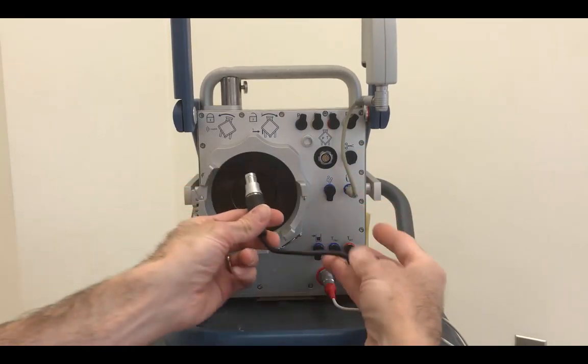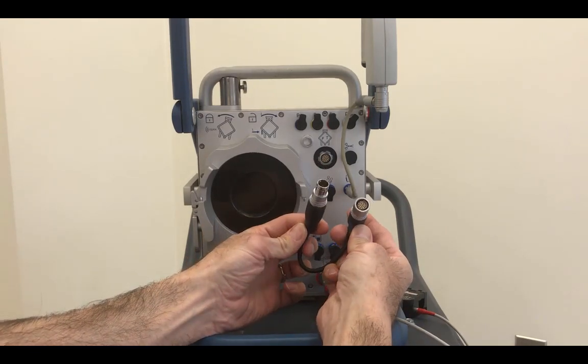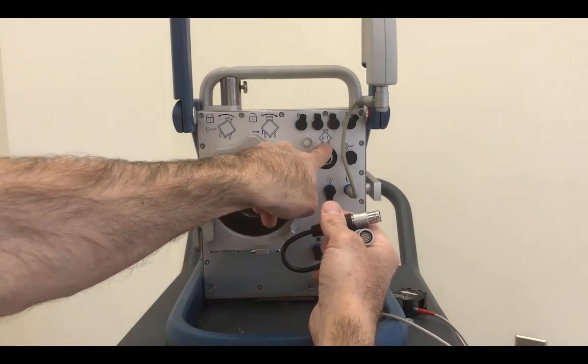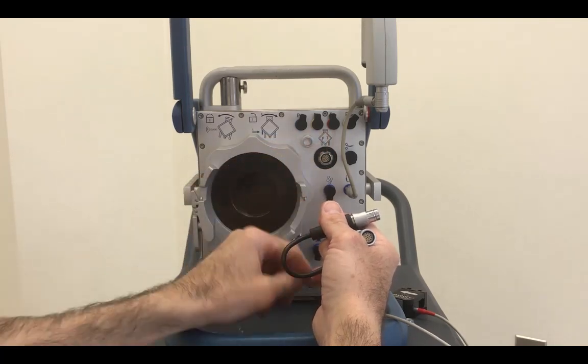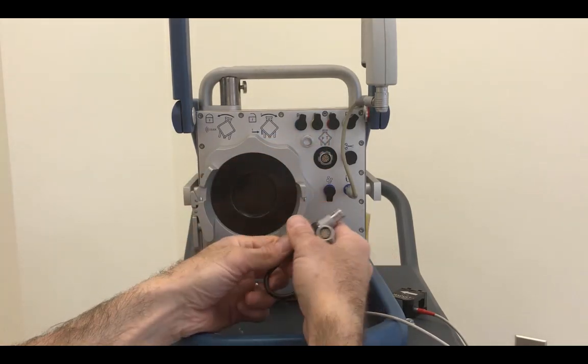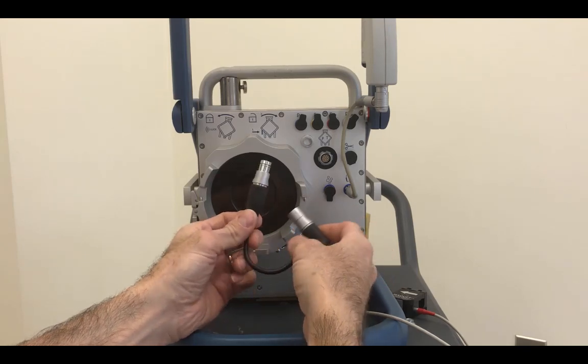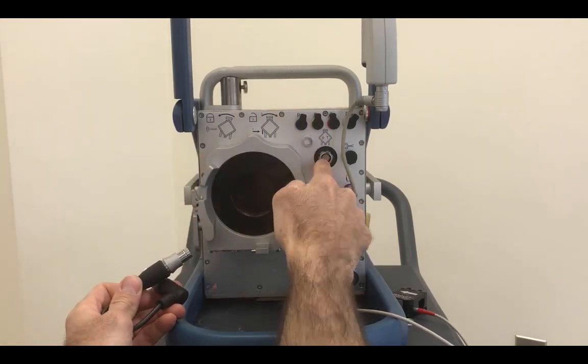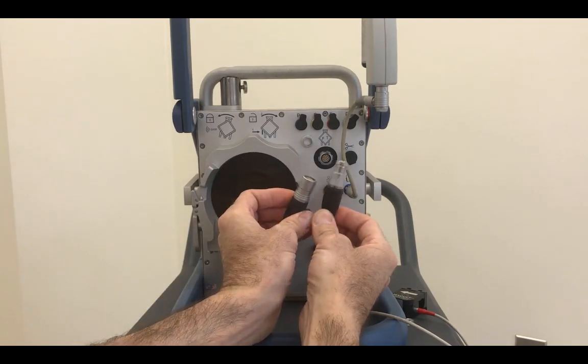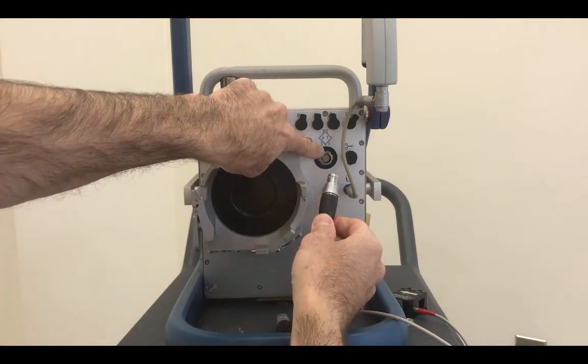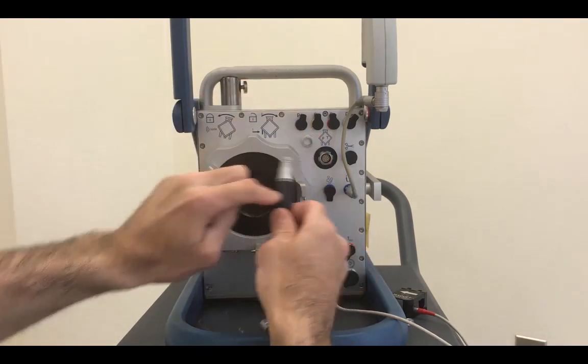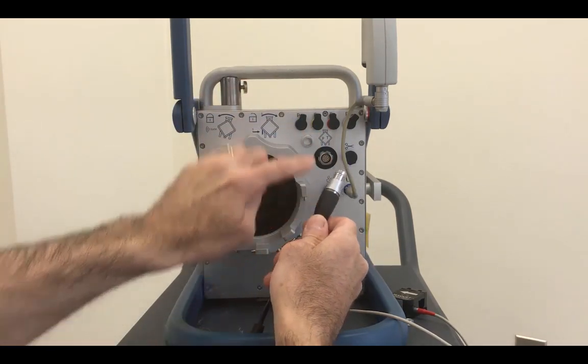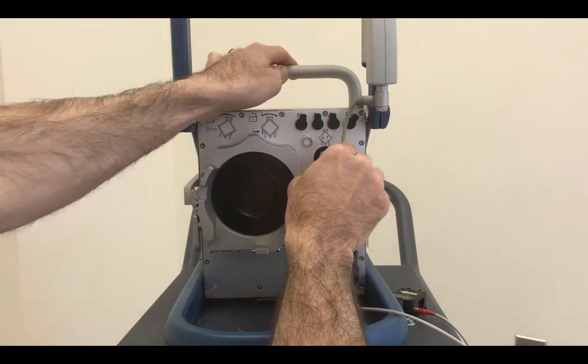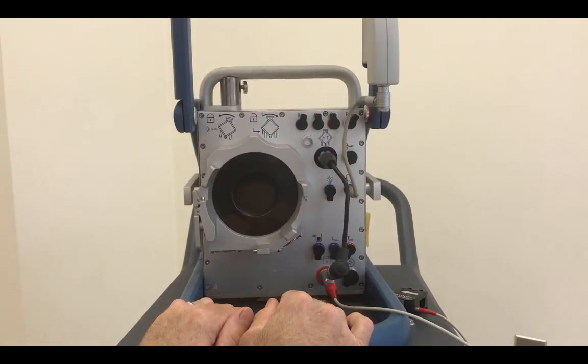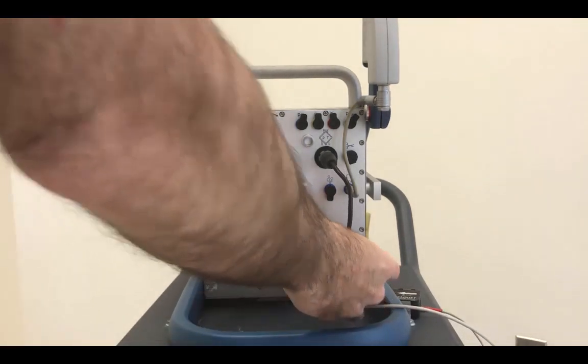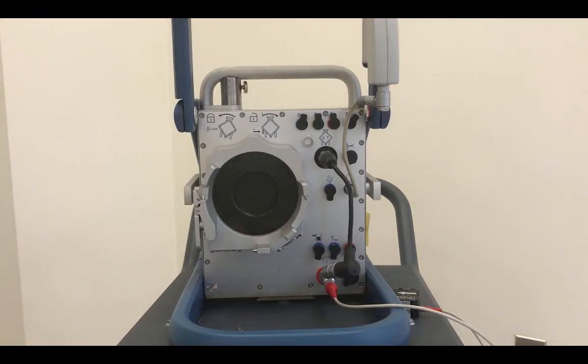The last piece we need for our setup today is going to be the data cable that connects to the oxygenator. The oxygenator has integral electronics for pressure sensors, and that data is going to come out of the unit here and go in that port there. So there's two ends to this port. The one with the red dot connects up to the red dot there. Black cable, black stripe. Go straight on. The other end of this is going to interface with the oxygenator. So let's put our oxygenator back in the unit.